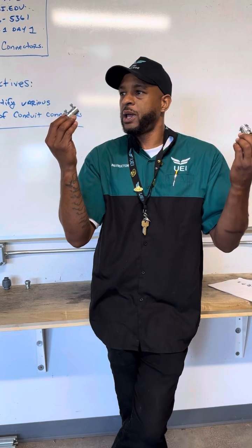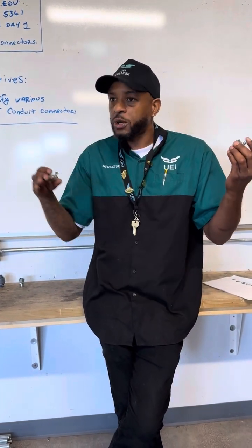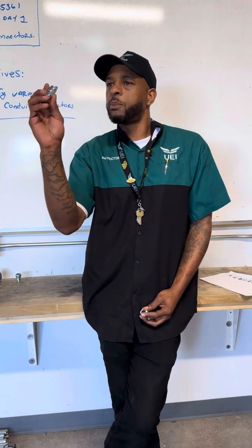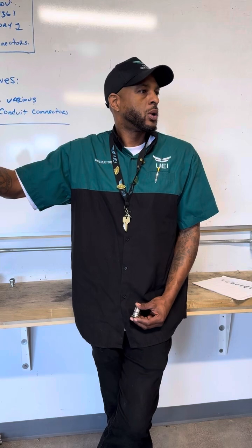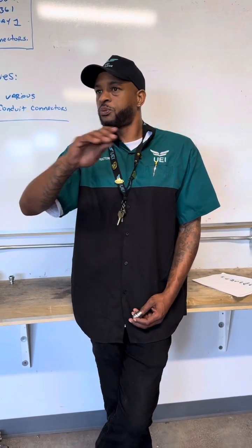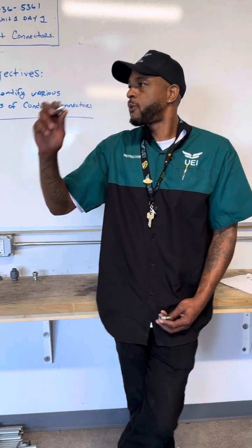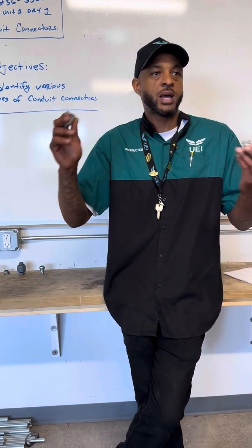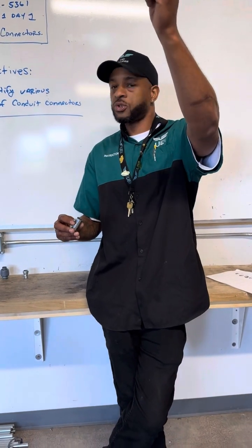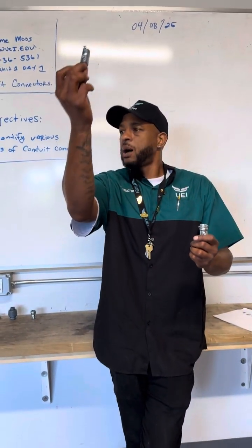So hypothetically speaking, if I'm doing a 30-degree offset at some concentric bends, right? If I put one coupling on in one location, I want the same location to have all couplings. I don't want nothing to be staggered. Just reminds me of using 1-hole straps or 2-hole straps. Everything in pipe bending must be formatted and nice and neat as possible, okay? So 1/2 inch connector, set screw connector, 1/2 inch coupling. These two go together.